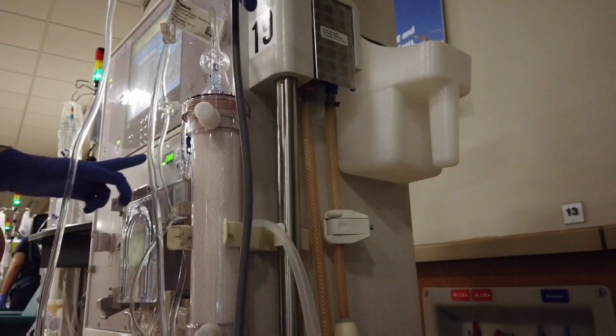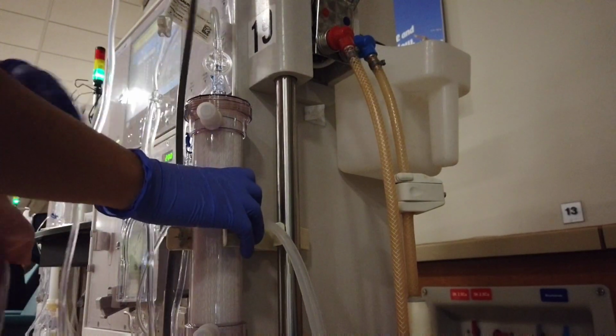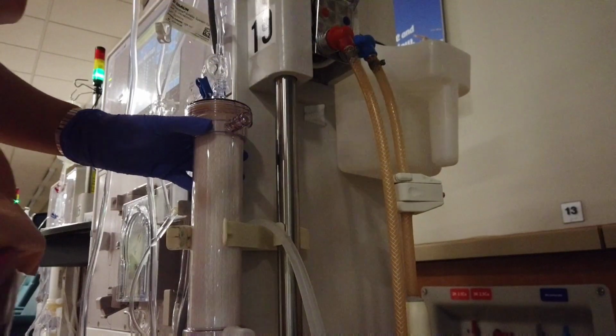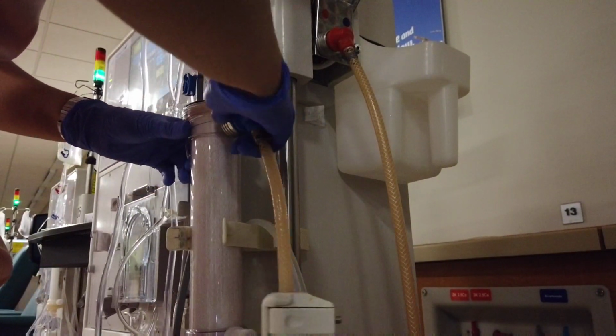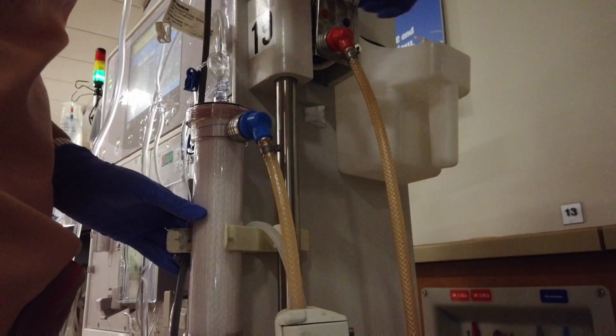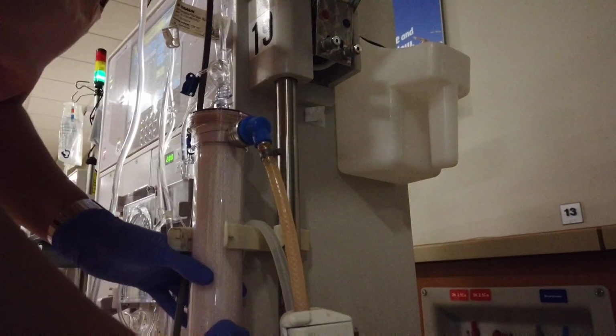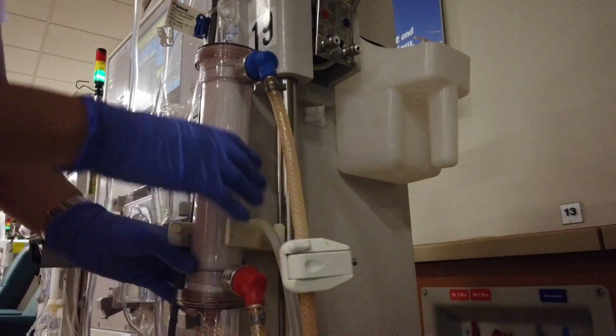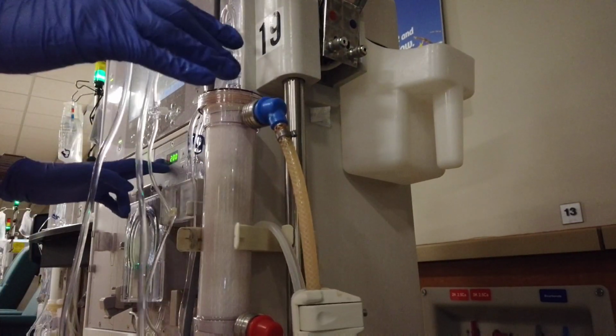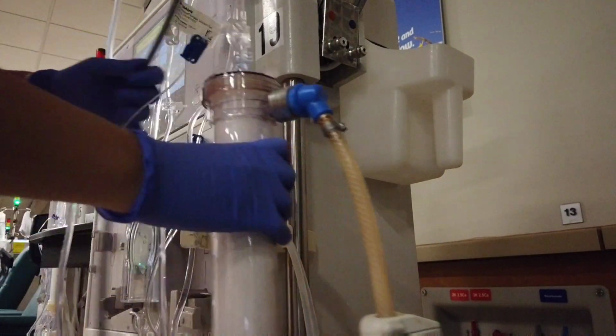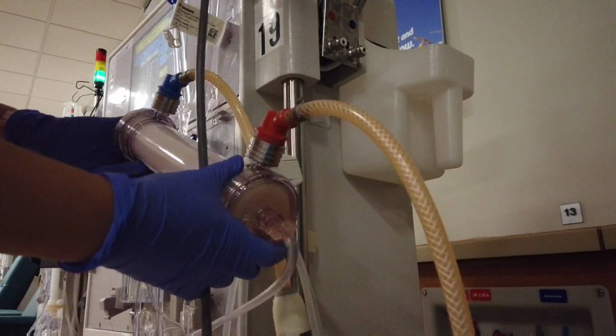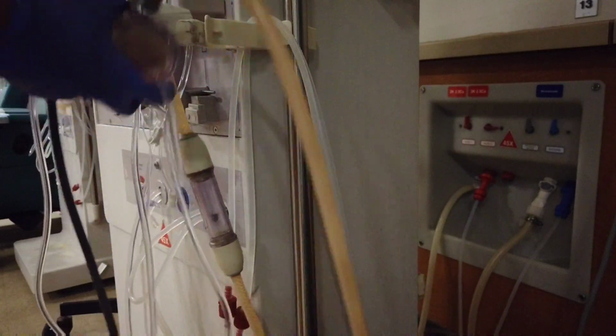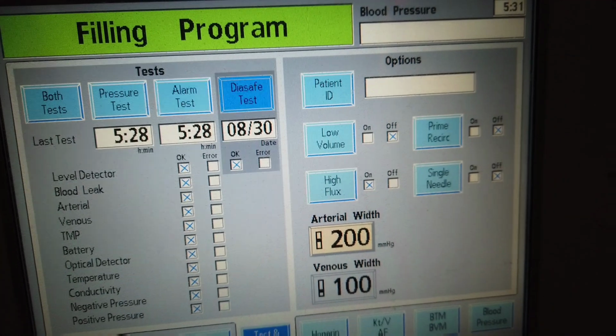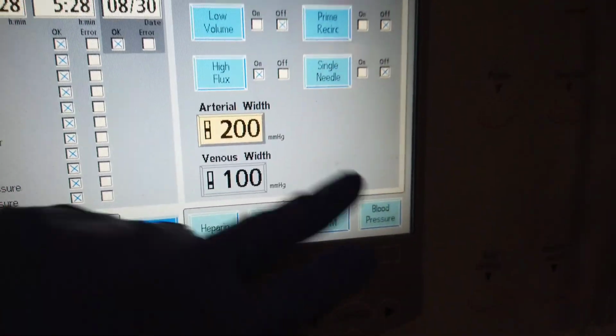Next step is to hook the coupling to the dialyzer. Blue up, red bottom. Do not forget to close the cover. Then tilt the dialyzer with the blue end downward to fill the dialysate side. Filling program message will also show in the screen. Also, after the test is complete, the patient ID can now be input.